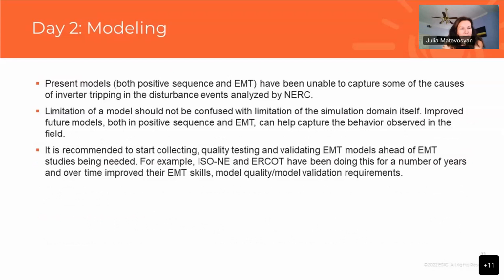It's been identified that present models, both positive sequence and EMT, have been unable to capture some of the causes of inverter tripping that we've seen in NERC disturbance events. Limitation of models should not be confused with limitation of simulation domain itself, so we shouldn't just all now jump and do only EMT studies. Future models can be improved to include some of these tripping behaviors that we've seen before, and this is relevant for both improving positive sequence and EMT domain models. And so these models need to capture things that we are seeing in the field. If those behaviors are included in the models and the relevant tool is used for relevant phenomena, then we should be good and see these events in the studies as well.